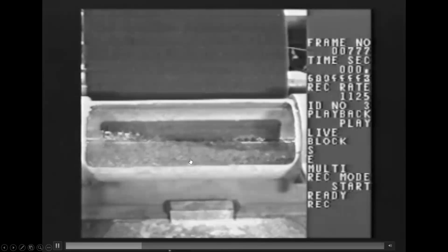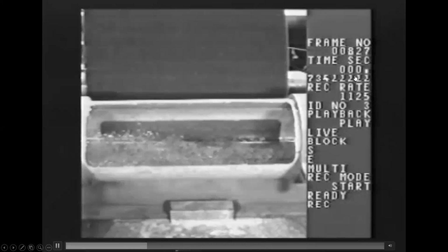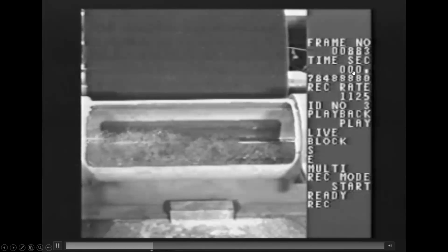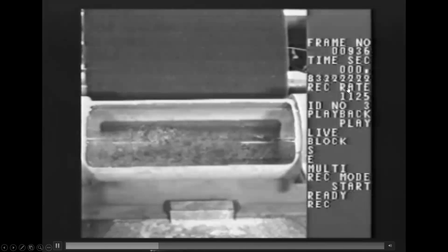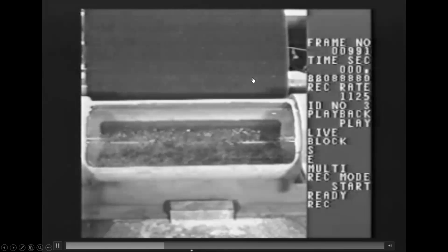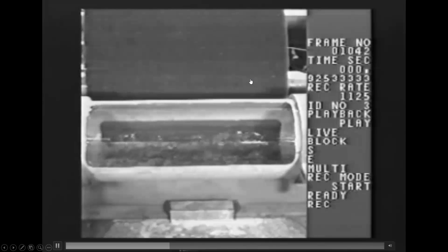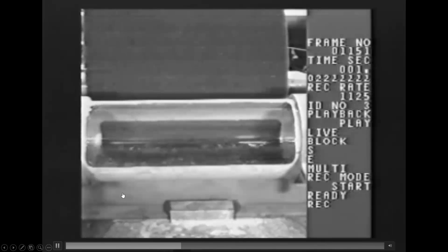Okay, you see that's a vapor cavity. Not even 1 second has passed. Okay, so we have this vapor cavity, the downsurge. The pressure went below the vapor pressure. 1 second passed. Now the water column returns.